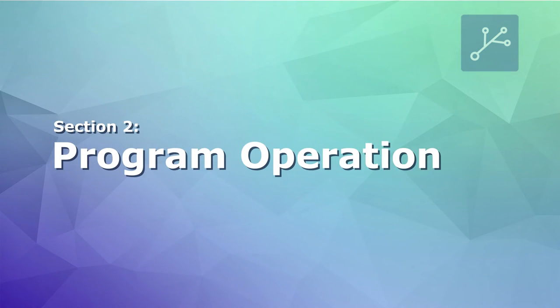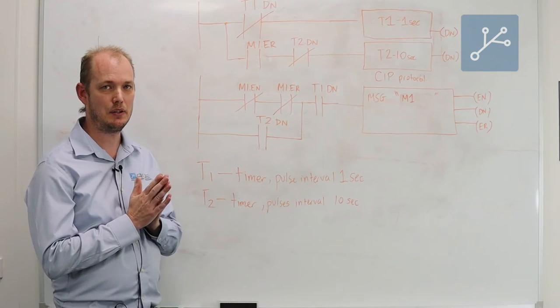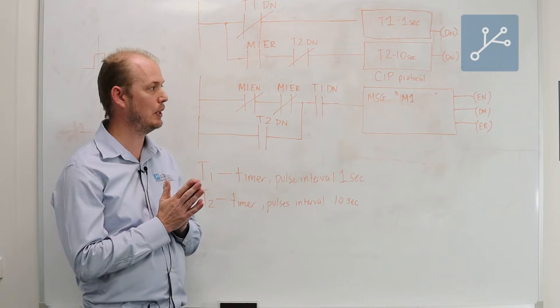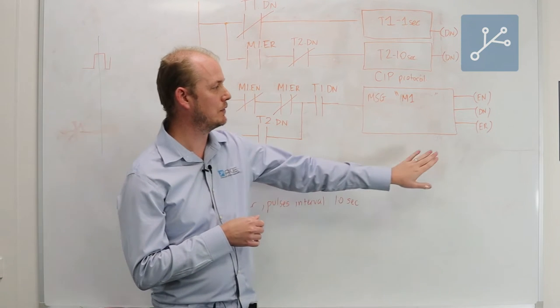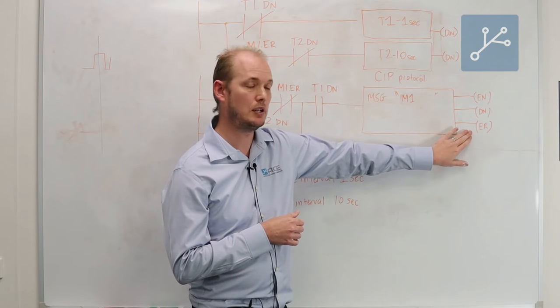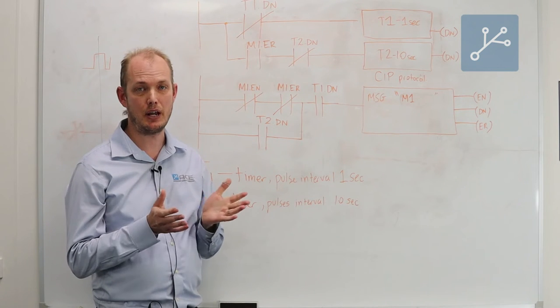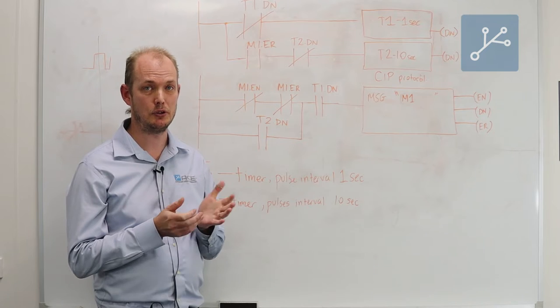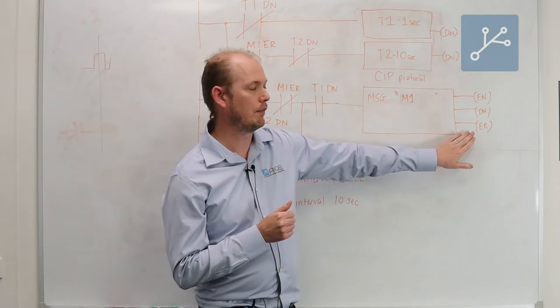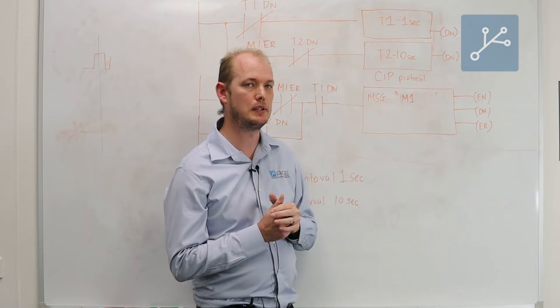In normal operation we're looking for the done bit because that means a successful message is being processed. An error bit obviously means there's something wrong with the message instruction. In terms of a network layout, it might be that the destination PLC is not reachable, so we'll get this error flag or error bit will be set.